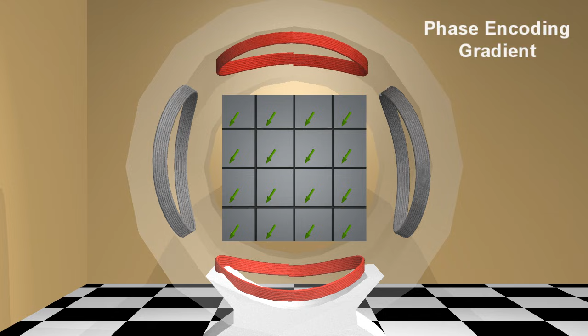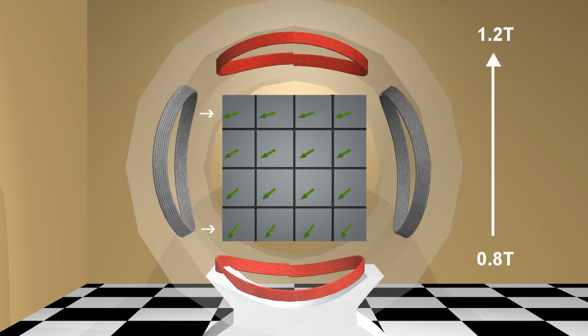To demonstrate the effect, we're going to slow down our net magnetic moments. The phase encoding gradient is briefly turned on, creating a gradient along the y-axis in this particular case, resulting in the magnetic moments at the bottom of the gradient slowing down and the ones at the top, where the magnetic field is higher, speeding up.